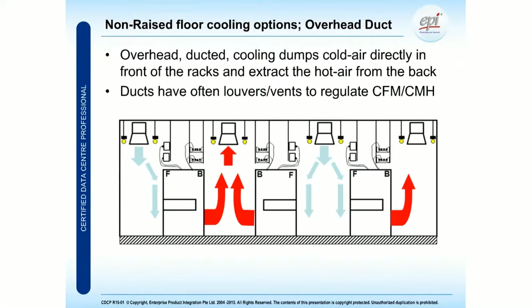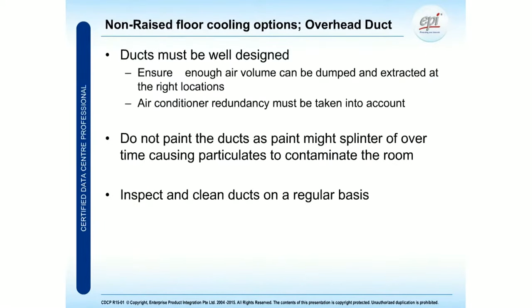Think about a data center that's been retrofitted in the past, maybe 5, 2, or 20 years ago, then cooling might become an issue. If cooling is becoming an issue, there are several systems available on the market that you can apply to get more cooling capacity at a particular rack spot. So the overhead ducts need to be well designed. Think about the amount of air, because if you have too little air, the temperature is no longer leading.